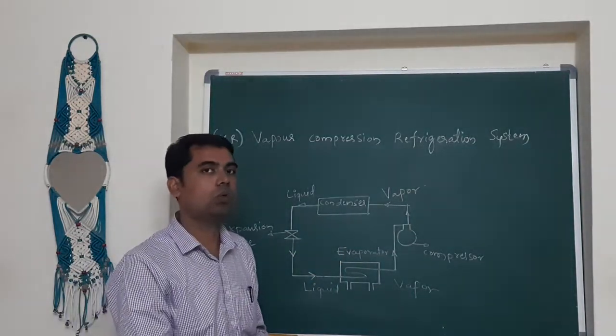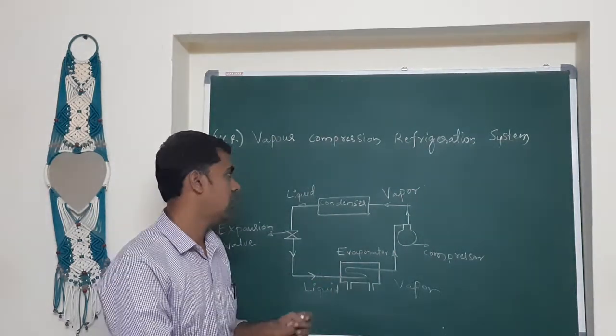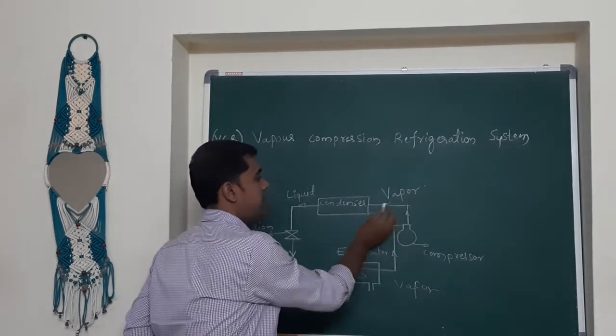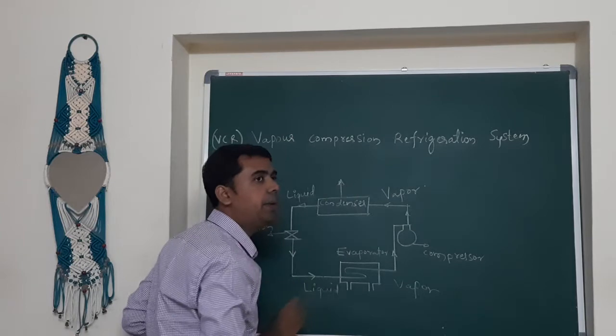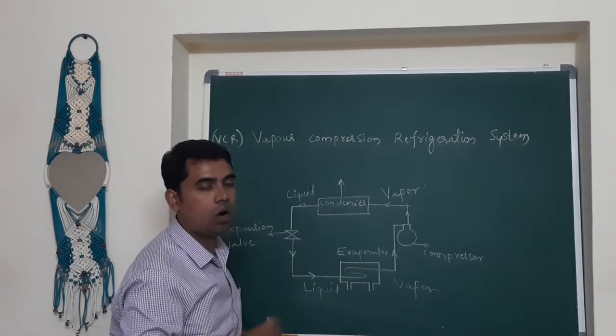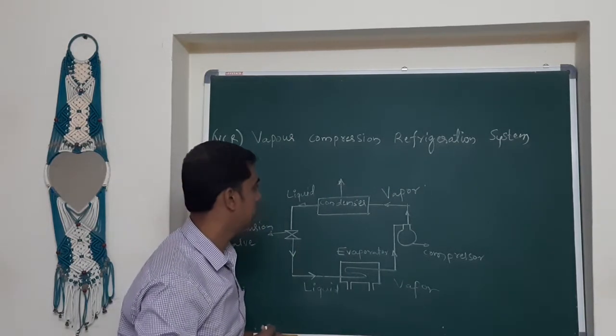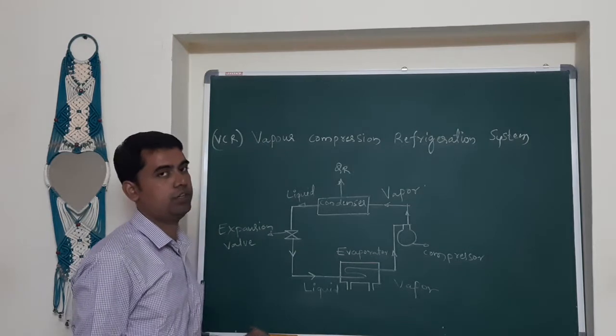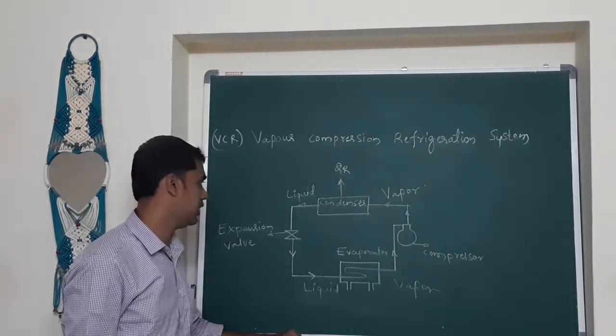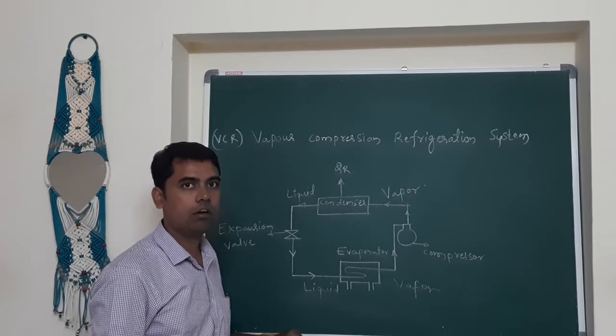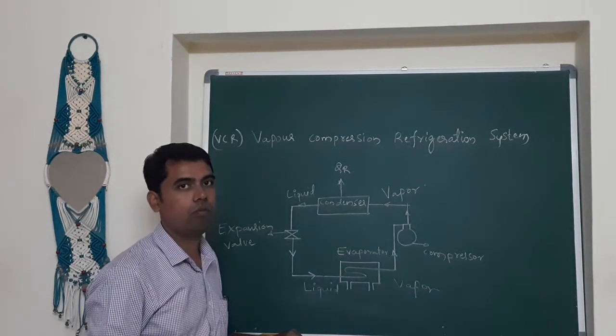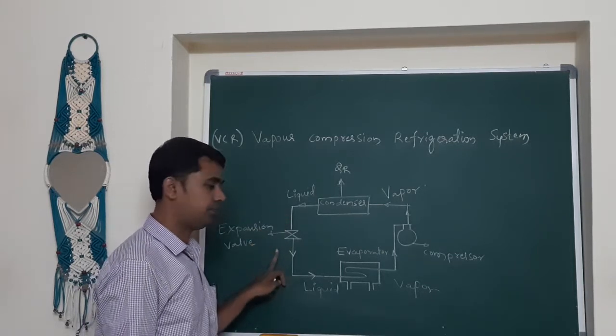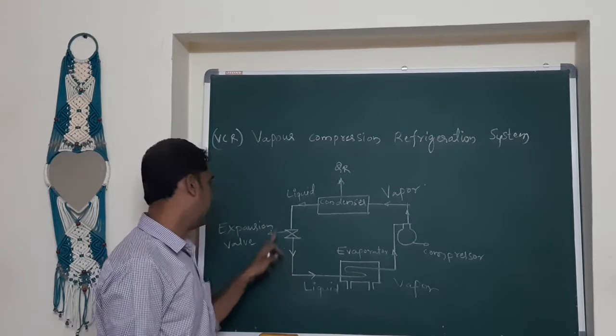The refrigerant then enters the compressor, where the vapor is compressed to high pressure. As it is compressed, it has a tendency to condense. It then enters the condenser, which is located outside the space to be cooled, where the high pressure vapor condenses and rejects latent heat of condensation.